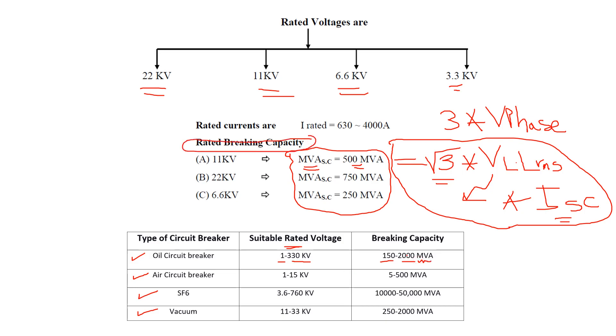Air circuit breakers operate from 1 to 15 kV — medium voltage only — with breaking capacities from 5 to 500 MVA. SF6 circuit breakers operate from 3.6 to 760 kV, covering medium, high, and extra-high voltage, with very high breaking capacities of 10,000 to 50,000 MVA. Vacuum circuit breakers cover 11 to 33 kV with 250 to 2000 MVA.